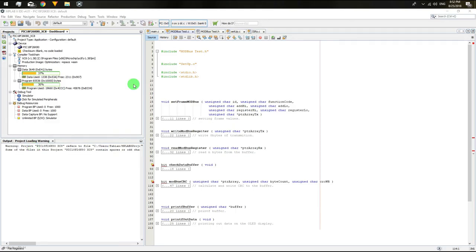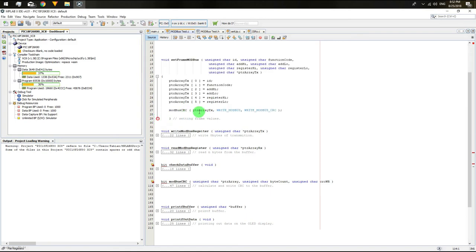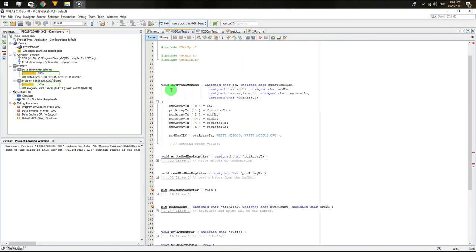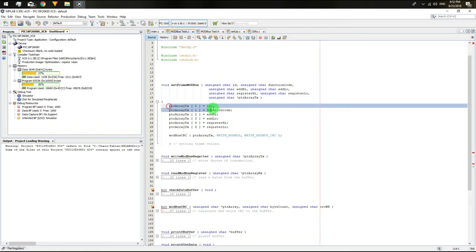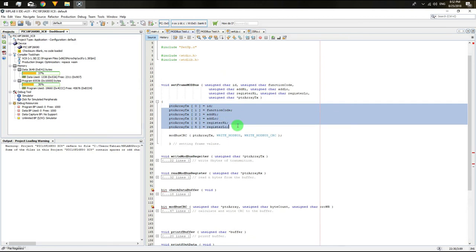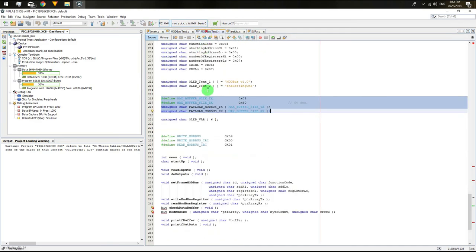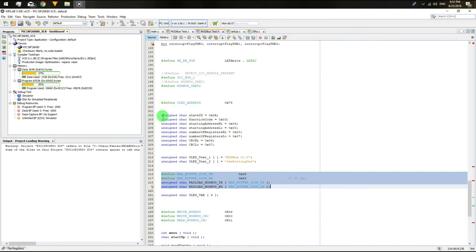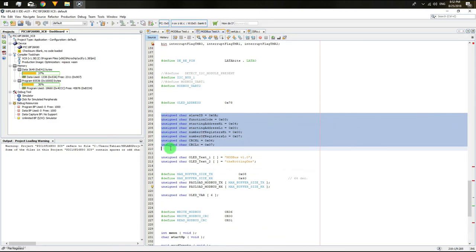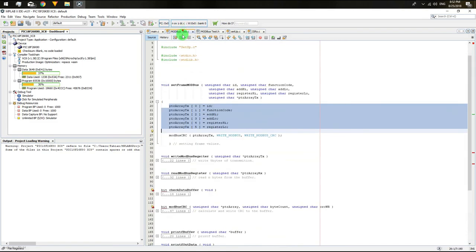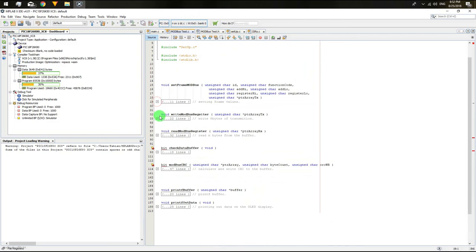Now for the Modbus function, the first is where you set the transmission array according to the Modbus RTU protocol. The first place is the slave ID, then the function, which in this example is number three, reading holding registers. Then two bytes holding the address where you want to start reading the data from the slave device, then another two bytes of how many registers you want to read. After that, you need to submit this information to the header file.